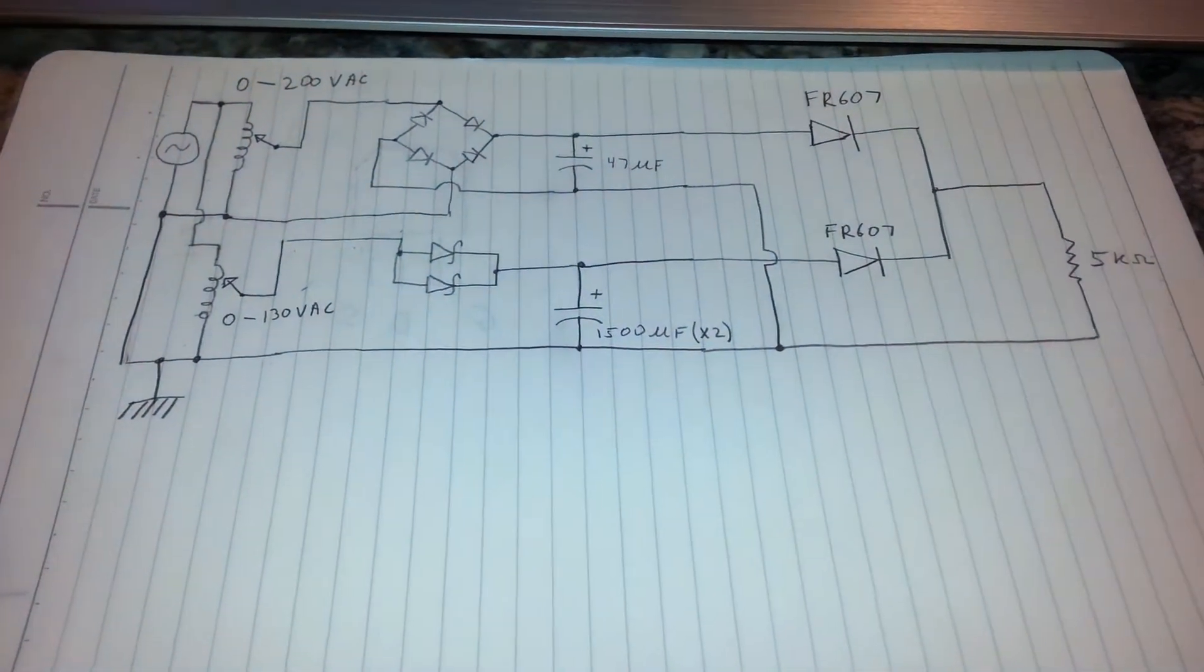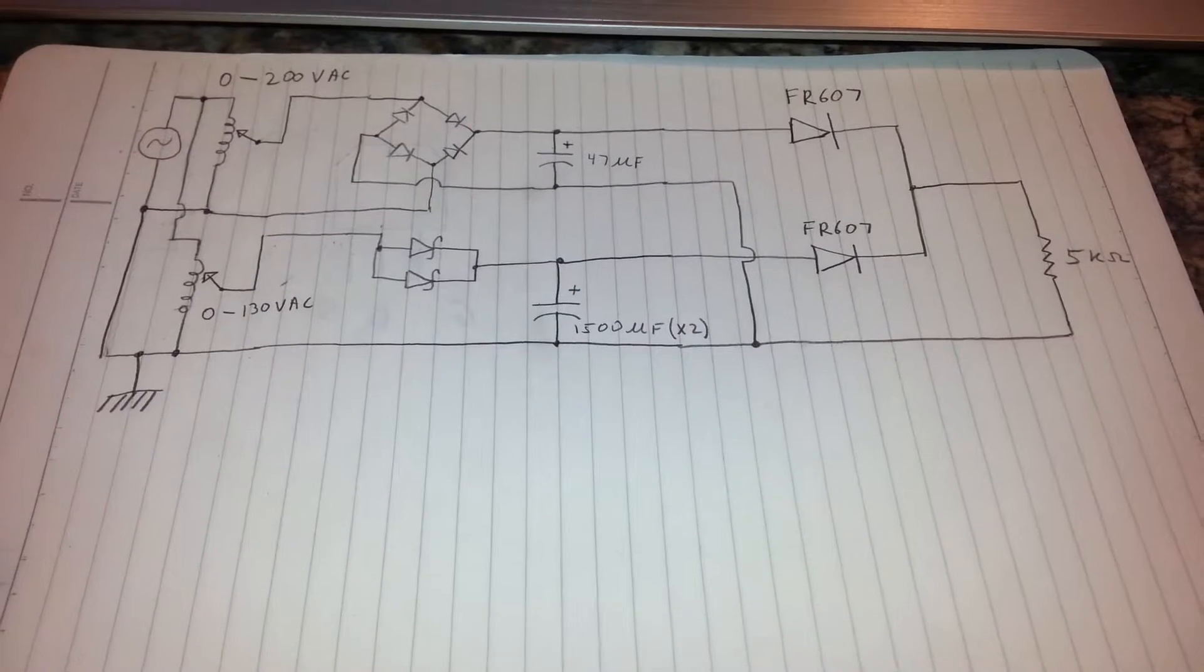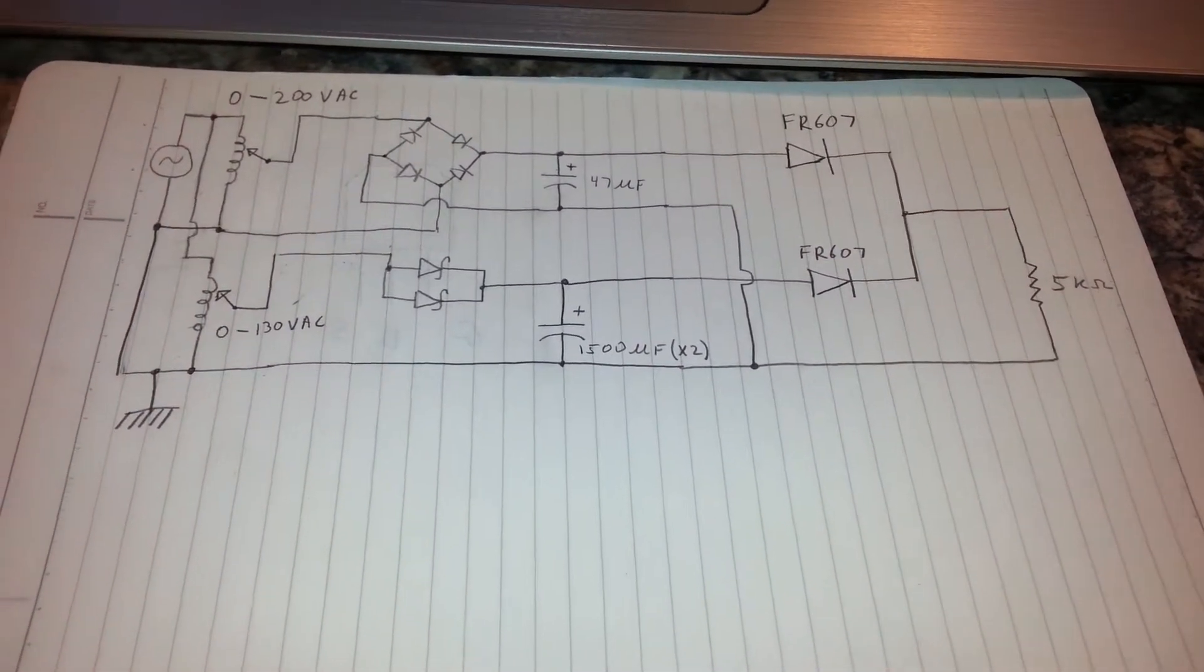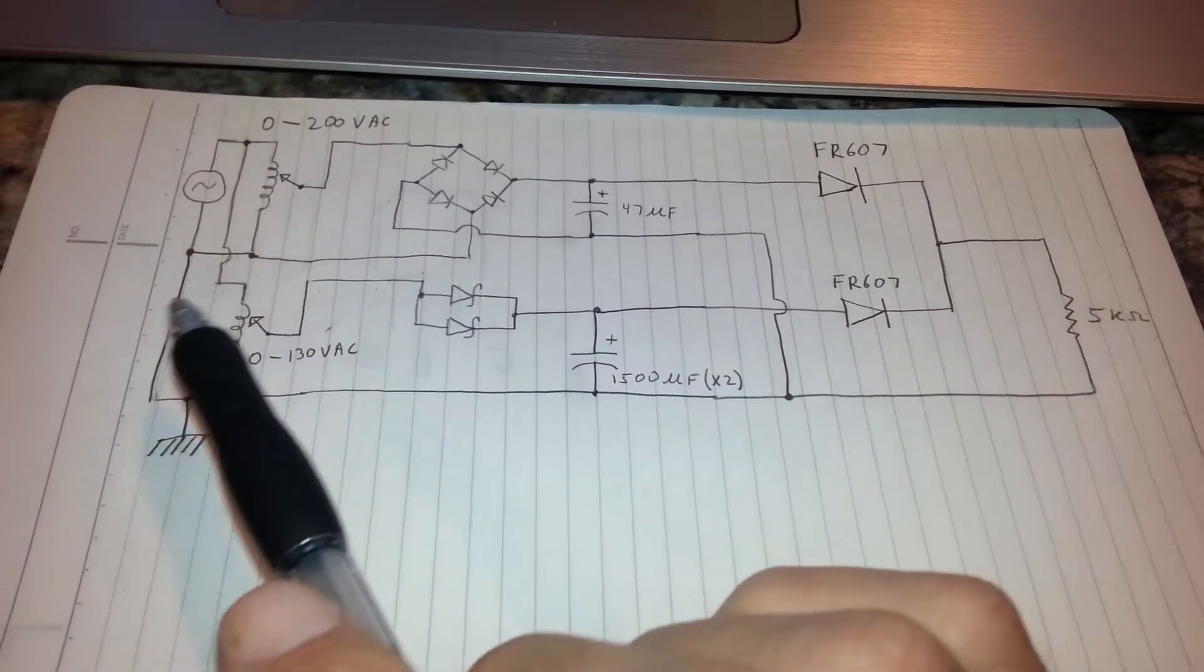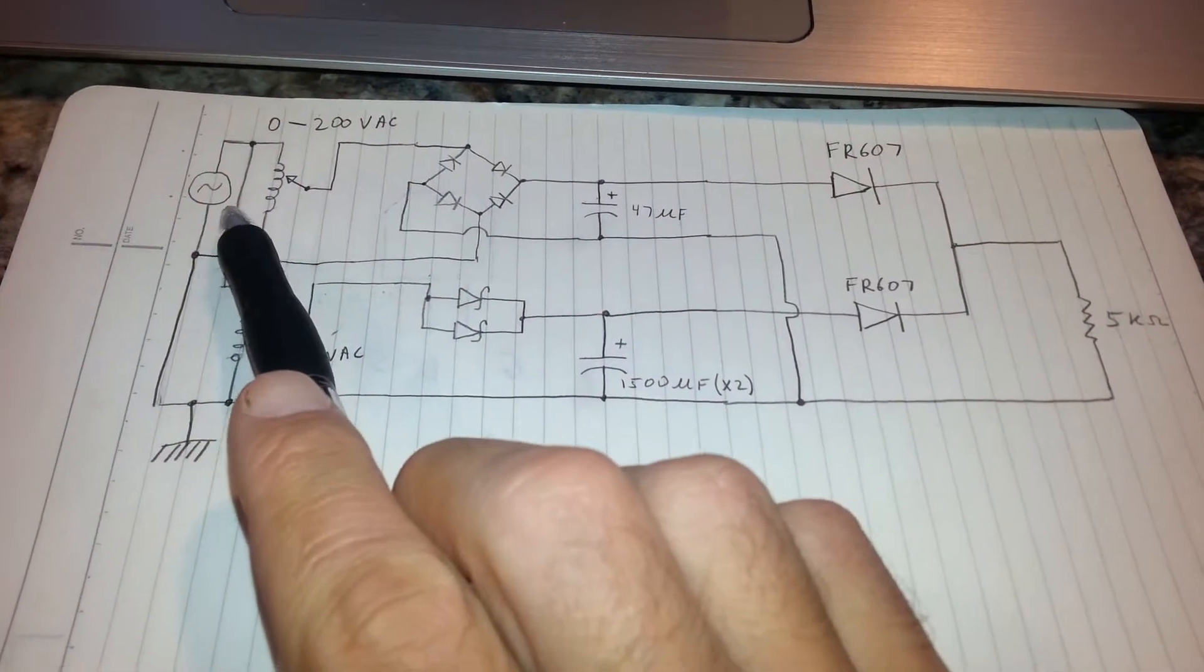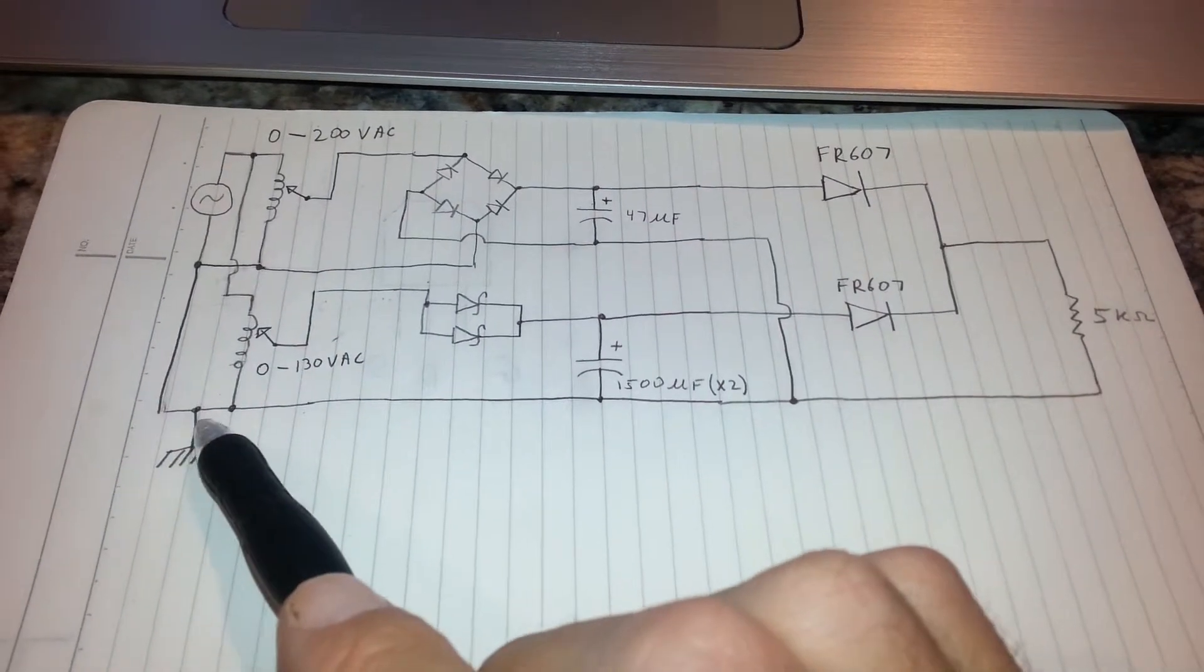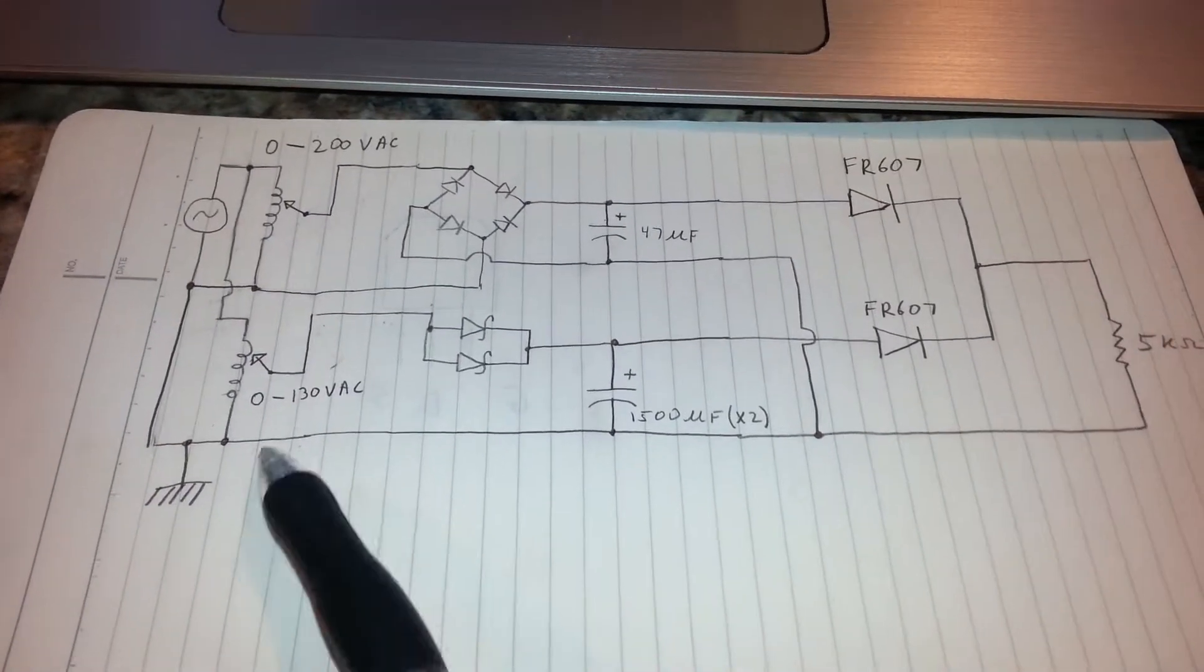So this is a schematic representation of my test setup in order to try to recreate the failure and understand the root cause. Going from left to right, I have a voltage source which represents the power from the house, and it's connected to the house wiring chassis ground or ground rod.